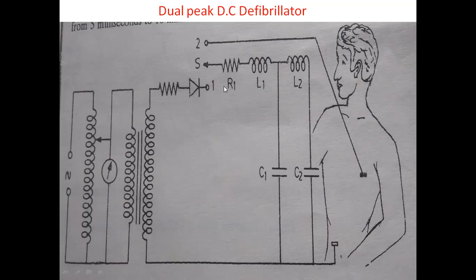In some advanced defibrillators, there is an option that once these capacitors are charged to their maximum extent, the switch connected to contact number 1 will be disconnected.